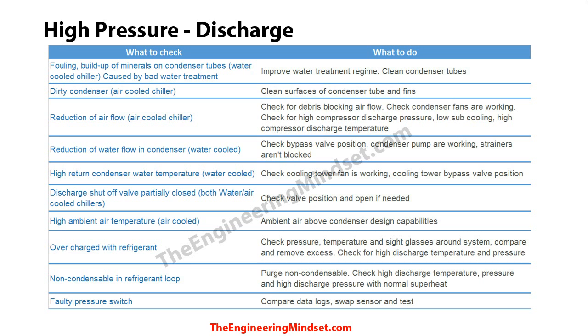Another problem that will cause the chiller to trip on high pressure is when the return condenser water from the cooling tower is too hot. Check that the cooling tower fans are working, that the bypass valves are properly aligned, and that the water is actually passing through the cooling towers to reject heat rather than bypassing them and returning directly to the chiller.